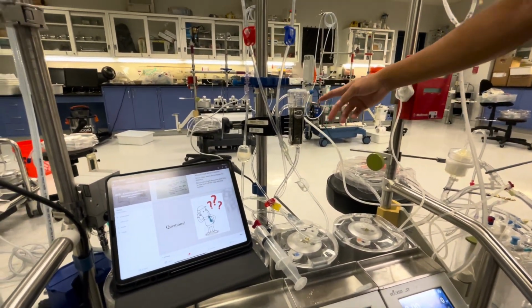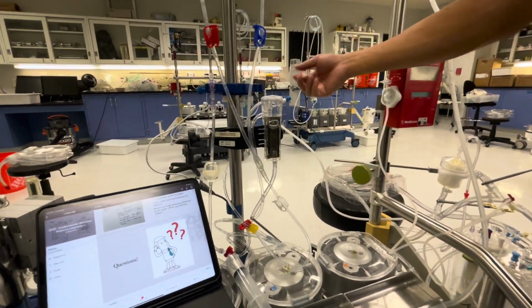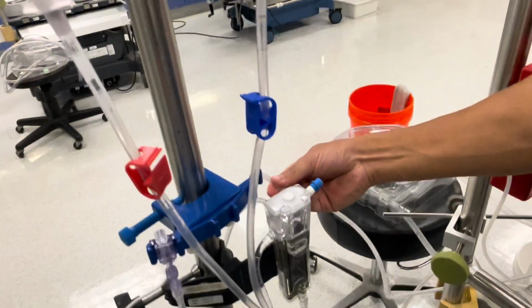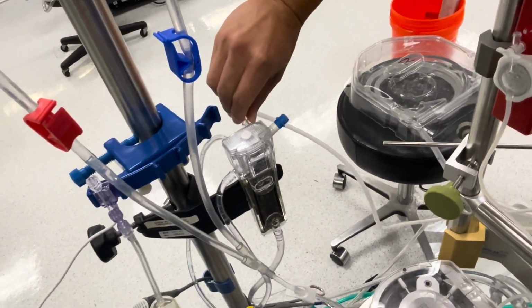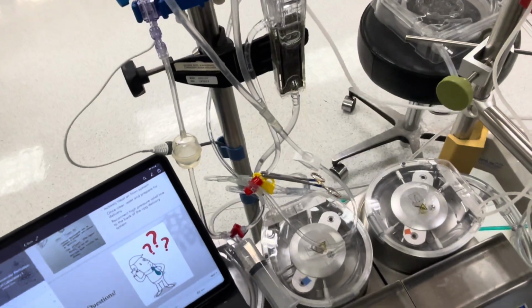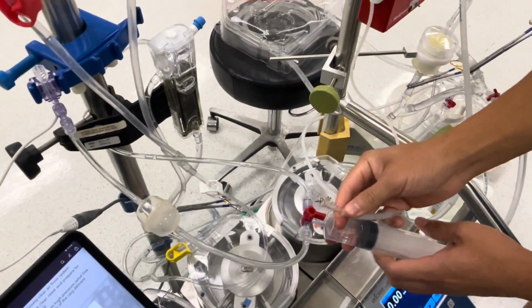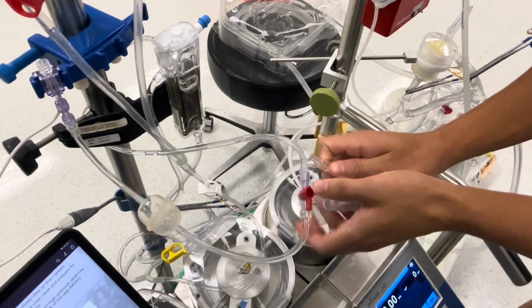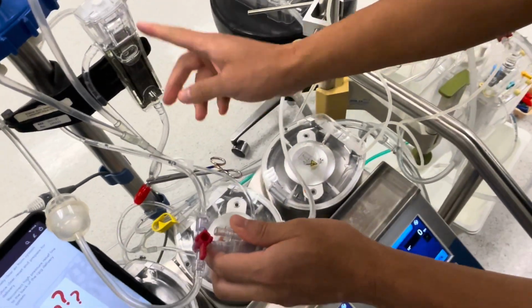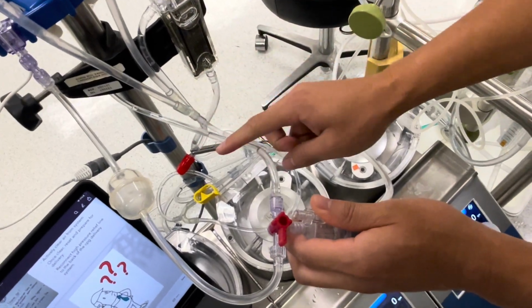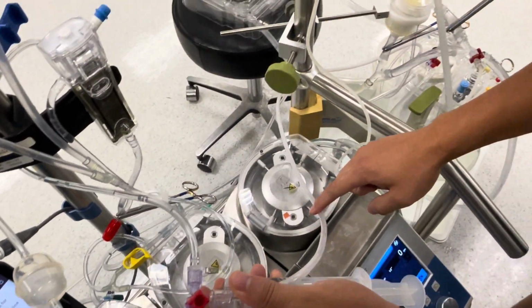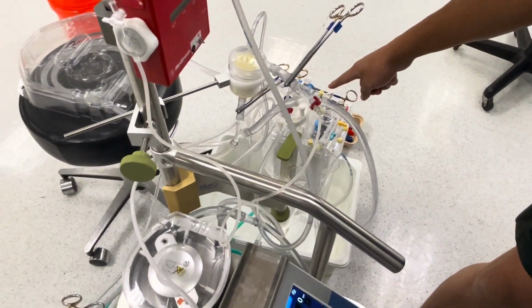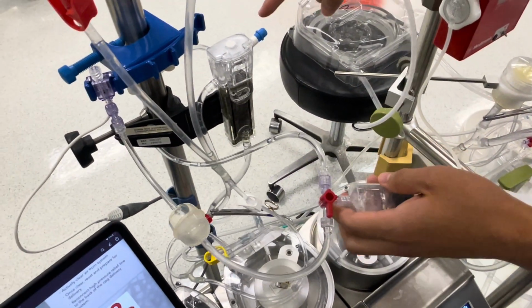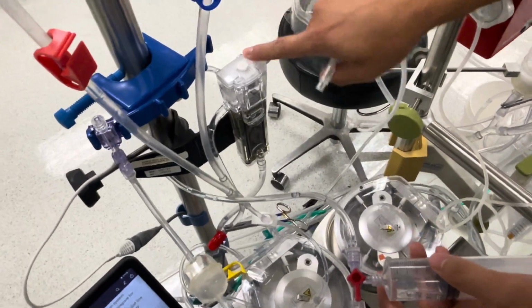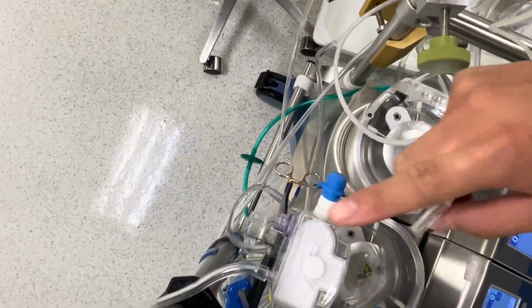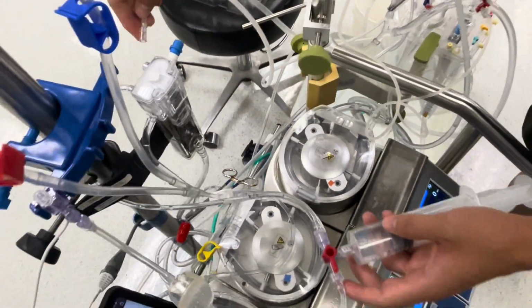If you did still have air in here, they explained it in class, you would take this high pressure line off from the Cardioplegia unit and attach it to where the syringe would be. So that way you'd have it just open to here, sending fluid through the pressure line into here, through the recirc line into your reservoir. The high pressure line shouldn't open because all the fluid should be going here, so there shouldn't be pressure building up in the system.